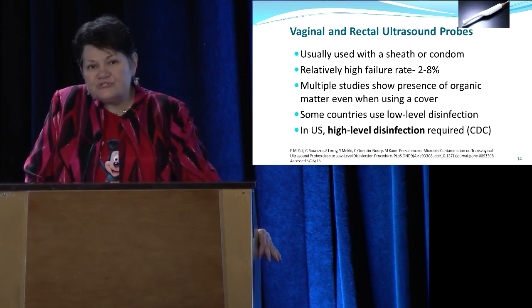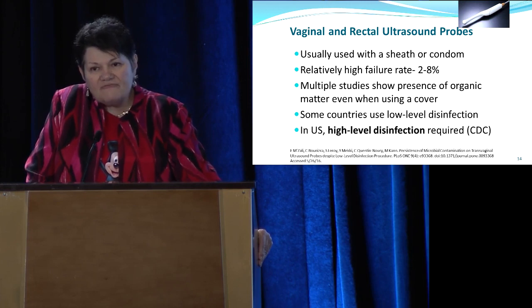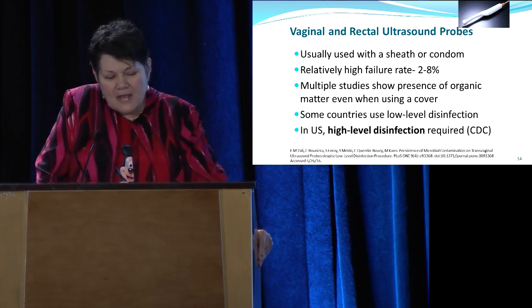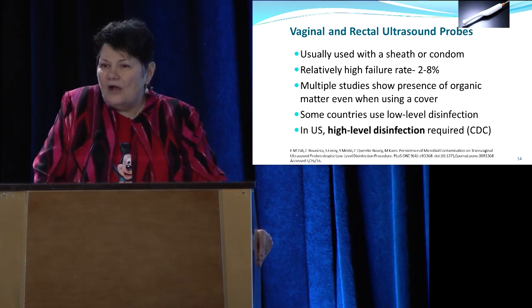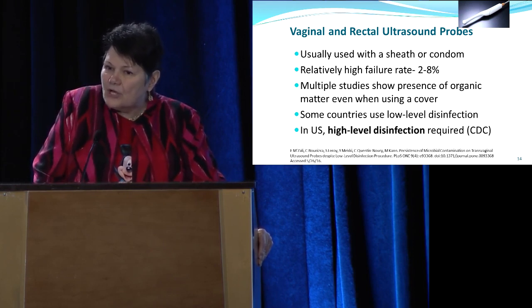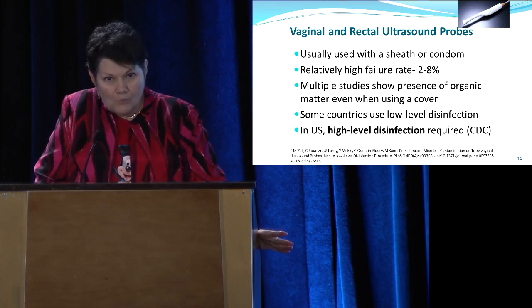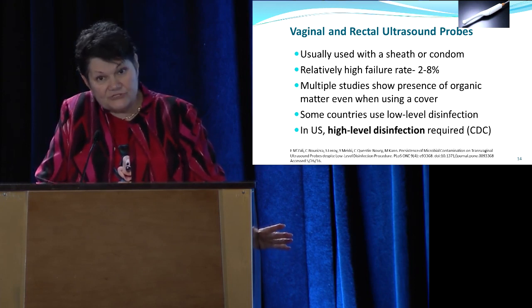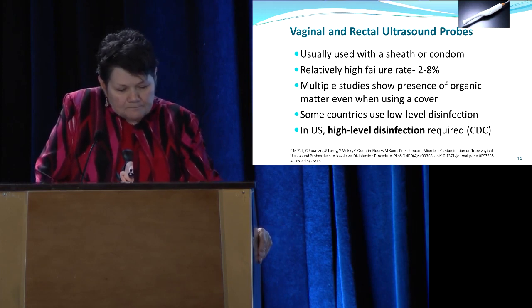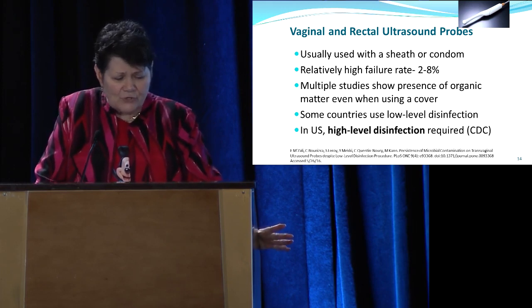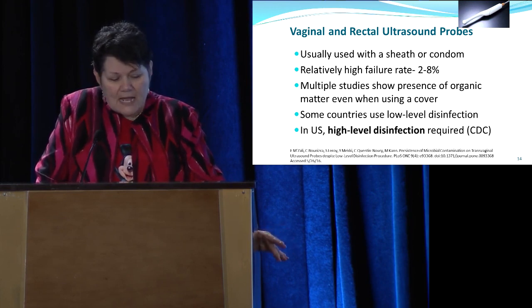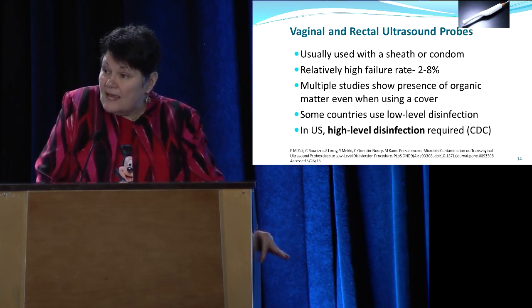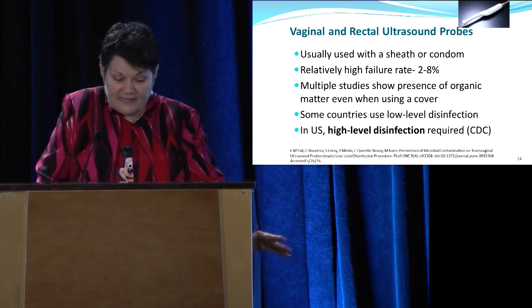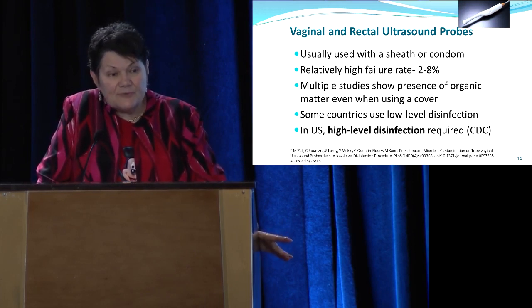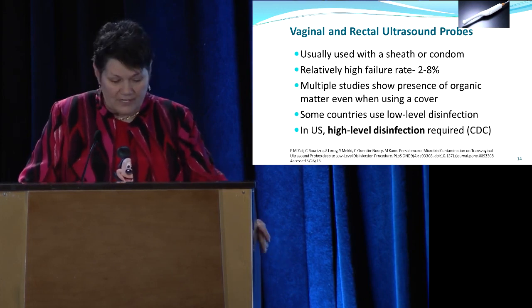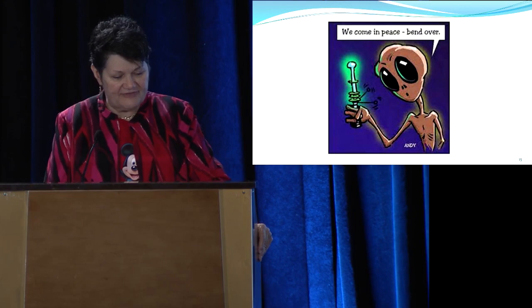The commercial sheaths that come with the products often have a very high failure rate, ranging from 2 to 8%. Often a good quality condom is a better cover than the ones that come with the devices themselves. So just a word to the wise. Multiple studies show presence of organic matter even when you're using the cover. Some countries in Europe do not high-level disinfect these. They low-level disinfect, but in the United States, the CDC requires, and the Spalding classification requires, at a minimum, high-level disinfection.